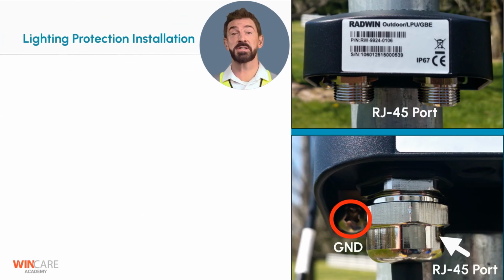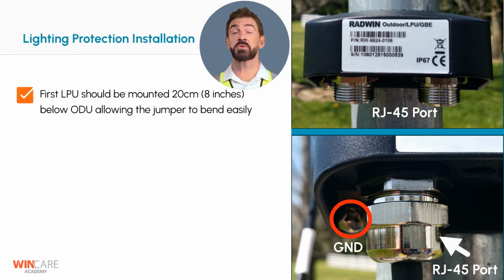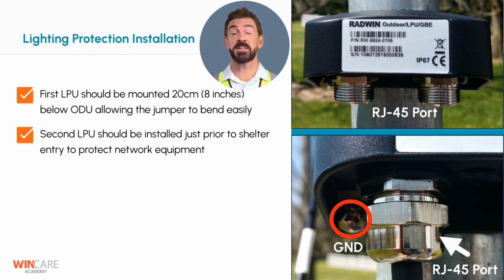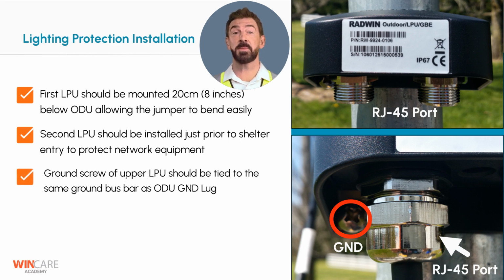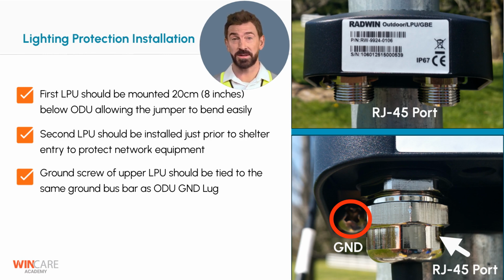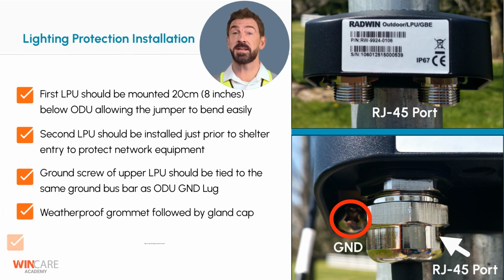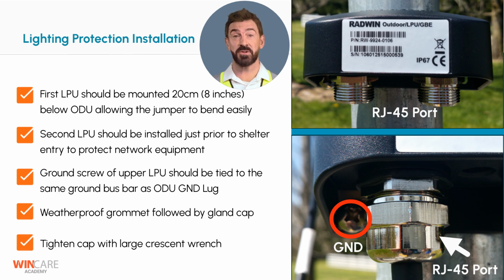In this example, we see a pole-mounted lightning protection unit installation. Mount the first LPU about 20 centimeters below the outdoor unit to allow a smooth cable bend. Place the second LPU just before the shelter entry to protect network equipment. Connect the upper LPU's ground screw to the same ground bus bar as the ODU to ensure proper continuity. Insert each connector fully until it clicks, add the weatherproof grommet, then tighten the gland cap gently using a large crescent wrench. Finally, label all cables and follow RADWIN's recommended LPU orientation and grounding guidelines for safe and reliable operation.